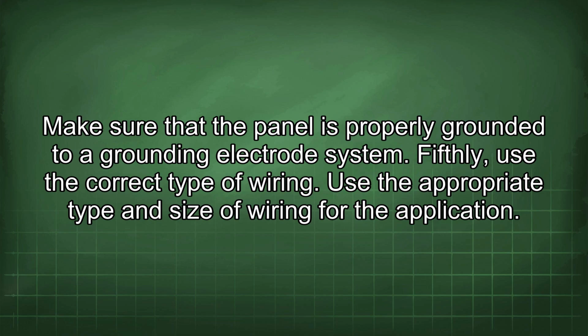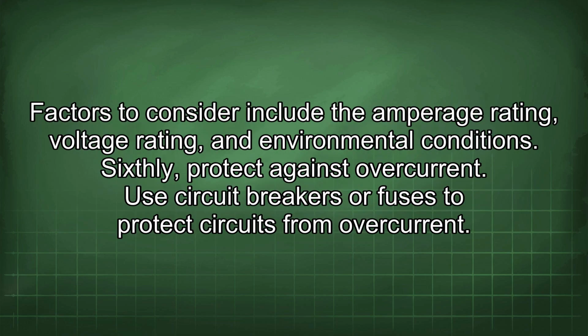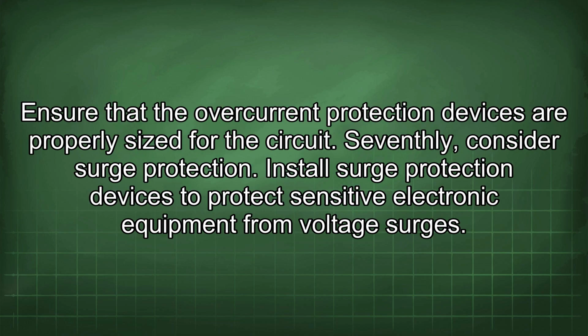Fifthly, use the correct type of wiring. Use the appropriate type and size of wiring for the application. Factors to consider include the amperage rating, voltage rating, and environmental conditions. Sixthly, protect against overcurrent. Use circuit breakers or fuses to protect circuits from overcurrent. Ensure that the overcurrent protection devices are properly sized for the circuit.